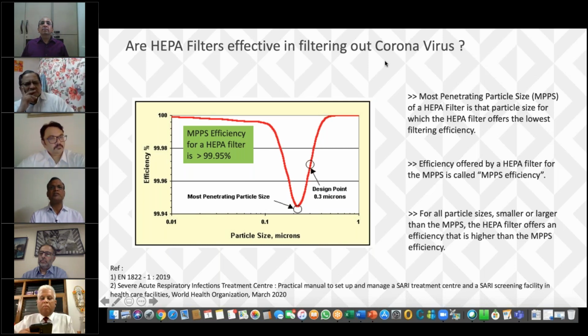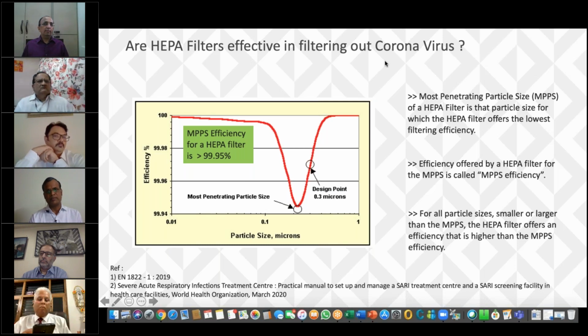to the level of 99.95% efficiency. But having said that, there is one big caution to add. The filters would have to be tested, because even if there is a microscopic rupture, which will not be physically seen, leakage of virus-laden particles can start happening. And the fitment of the filter is also so important that it will have to be mounted and then tested at the site, so that we ensure a perfect fitment without any leaks through which the contaminants can leach out. This is a caution that we need to take, but as such the HEPA filter is perfectly capable of filtering out these particles. So that is about HEPA filters. Can we move to the next slide?